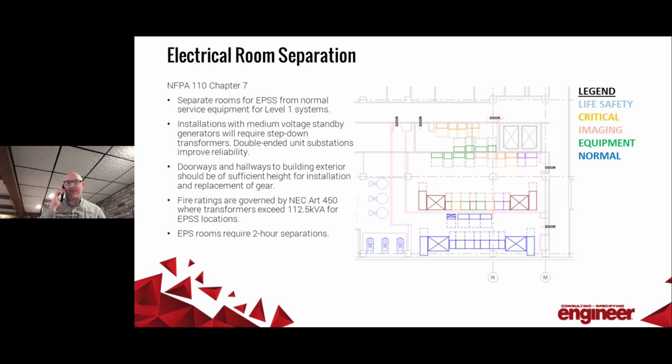The 2-hour requirement for an EPS depends on where my generator breakers are. Maybe those generator breakers are remote and located in this room. We could talk a lot more about that, but from a general standpoint, read all of Chapter 7 and then also refer to the difference of the EPS and the EPSS and where that difference actually lies.